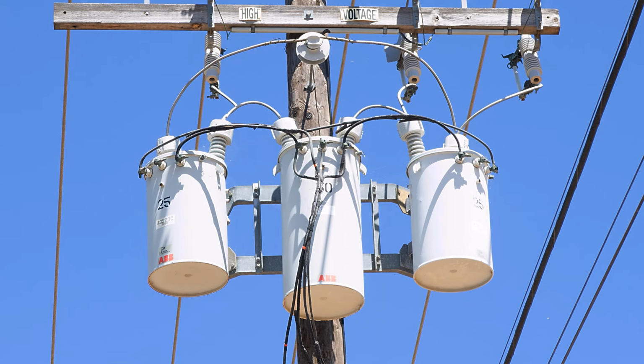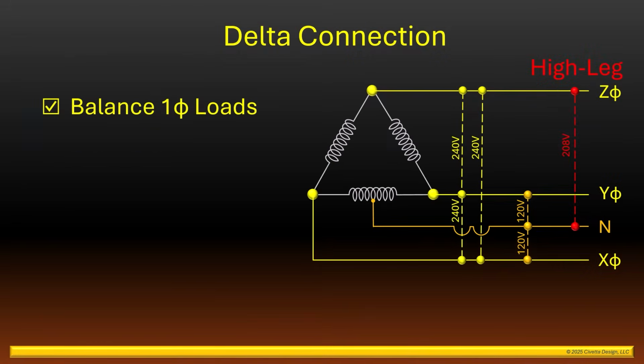It's also important that the high leg phase is properly marked and identified. You can see here the line worker that installed this bank has marked the high leg phase with orange tape, here, here, and here. Not marking the high leg is probably how it came to be known as the stinger.